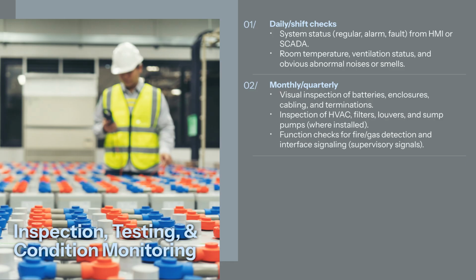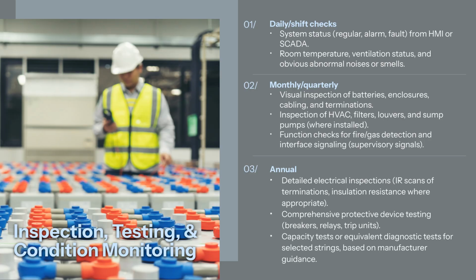Inspection of HVAC, filters, louvers, and sump pumps where installed. Function checks for fire and gas detection and interface signaling, supervisory signals. And finally, annual: detailed electrical inspections, IR scans of terminations, insulation resistance where appropriate. Comprehensive protective device testing, breakers, relays, trip units, and capacity tests or equivalent diagnostic tests for selected strings based on manufacturer guidance. NFPA 70B supports the use of condition-based and predictive techniques, including thermography, partial discharge, online monitoring, and advanced analytics to refine intervals and focus resources.